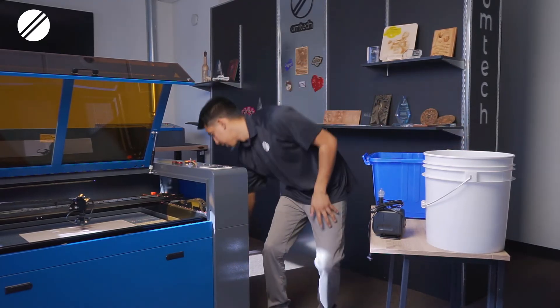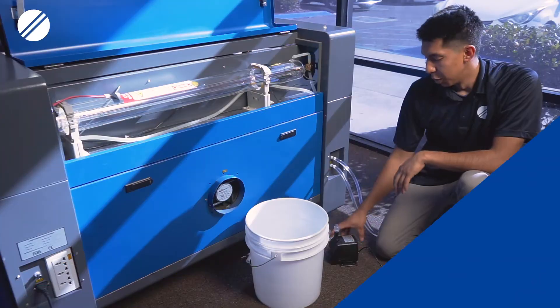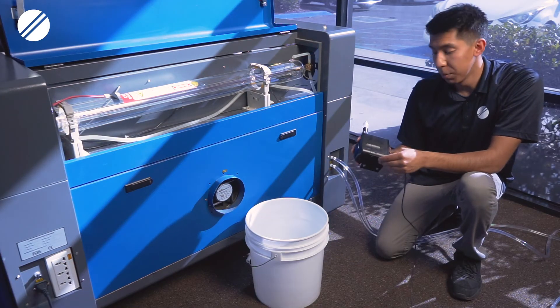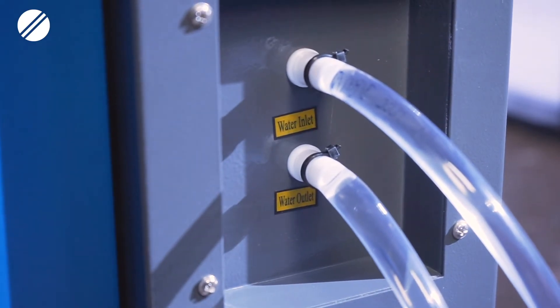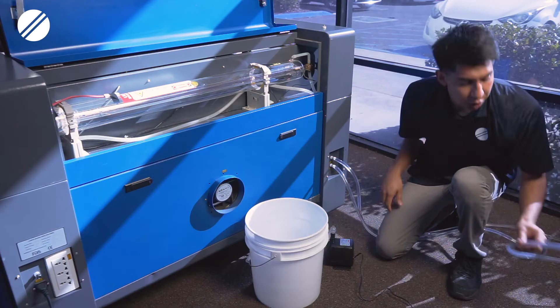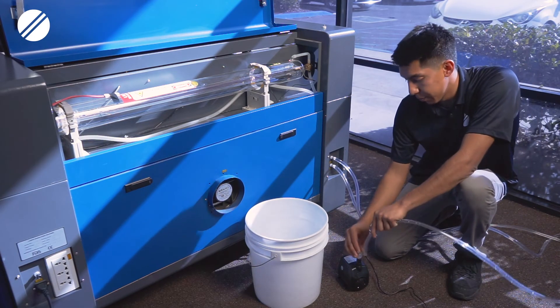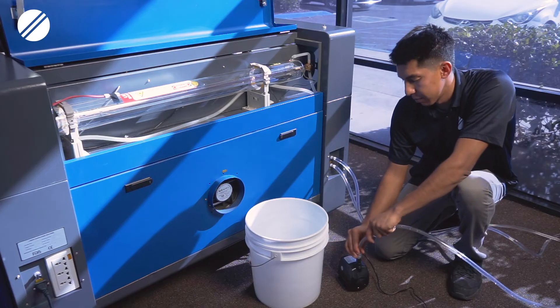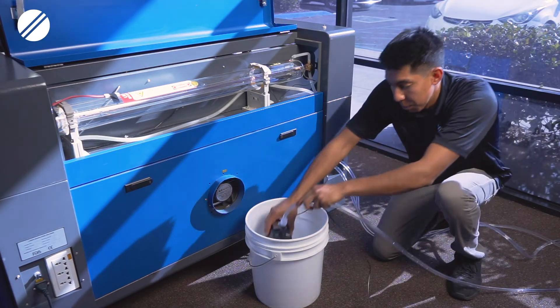For cooling, we recommend distilled water with no additives. So for the setup of your standard water pump, you would take one of the water hoses provided, you will connect one of them to the water inlet connection of the machine, you will connect that hose to the water pump itself, and you can then place the water pump inside the bucket.